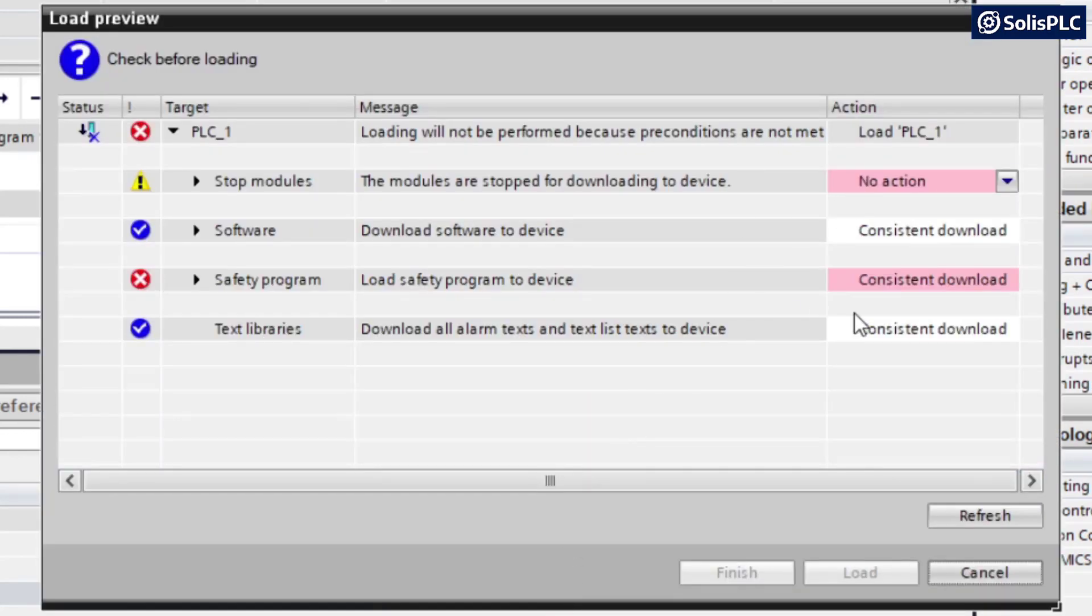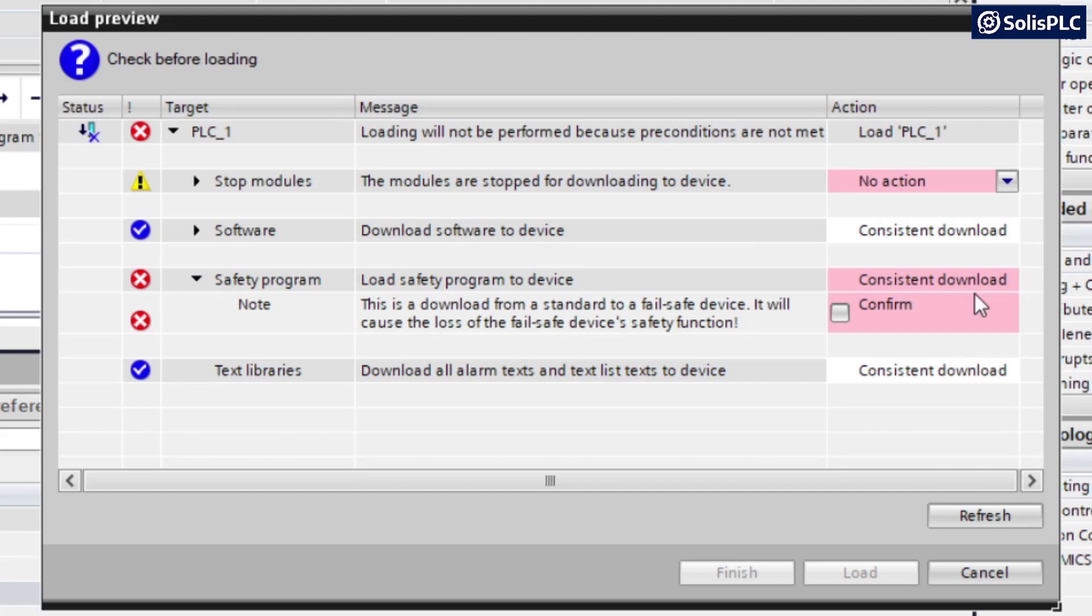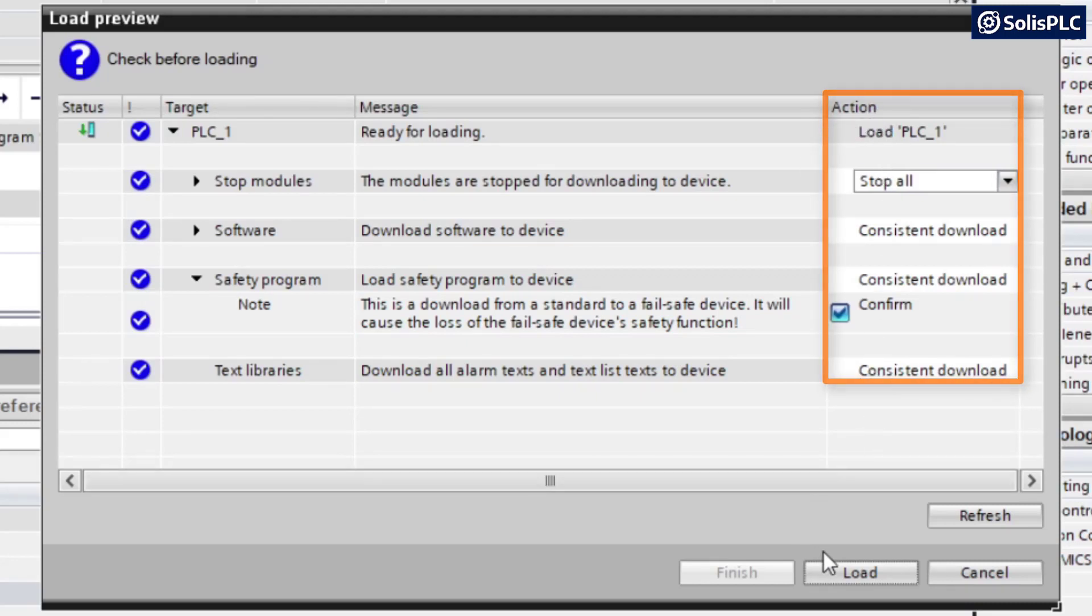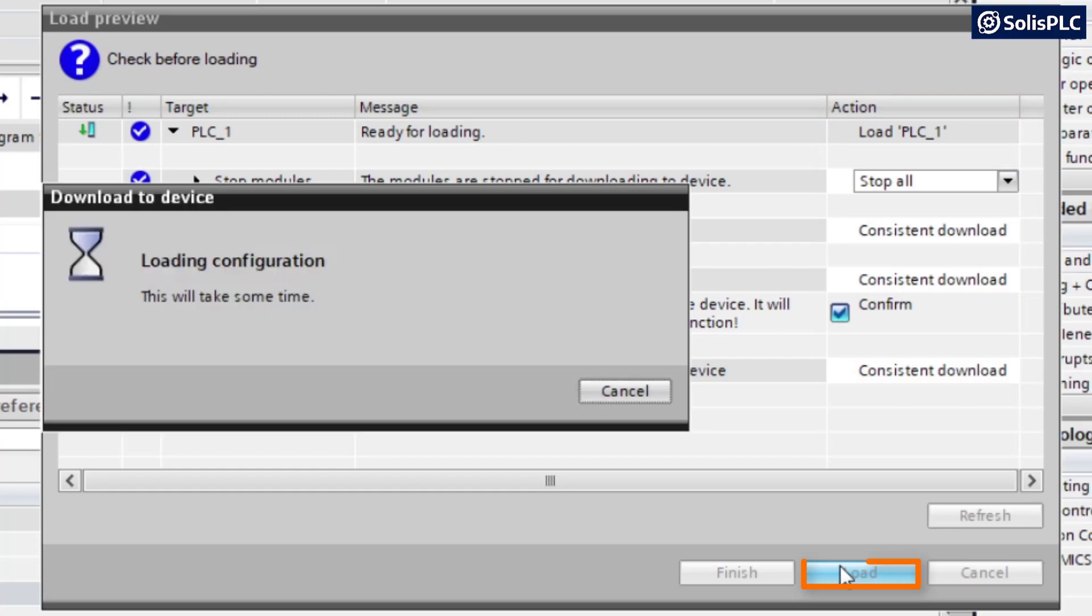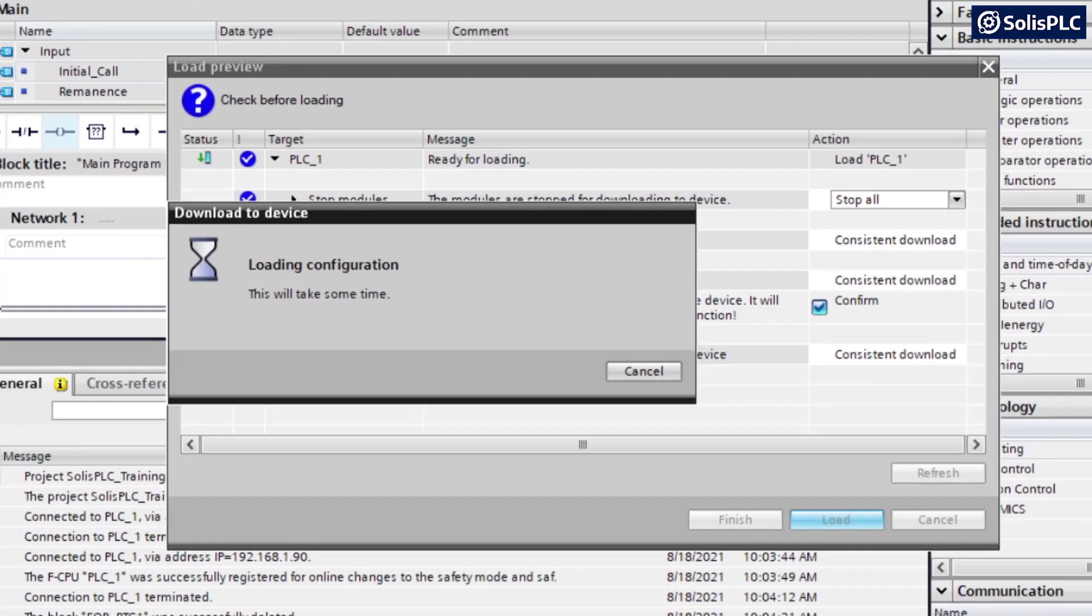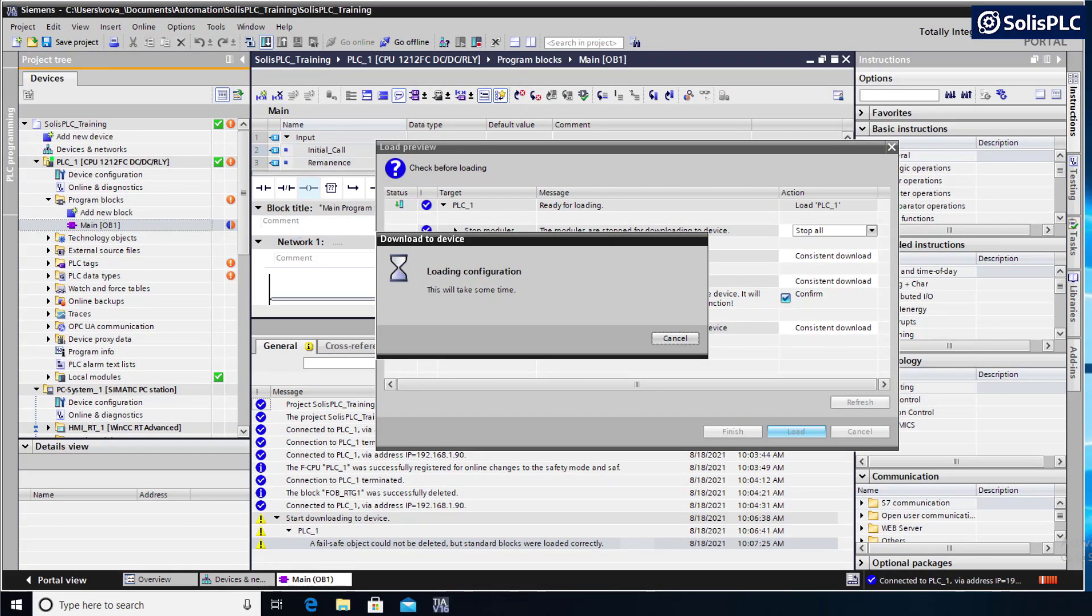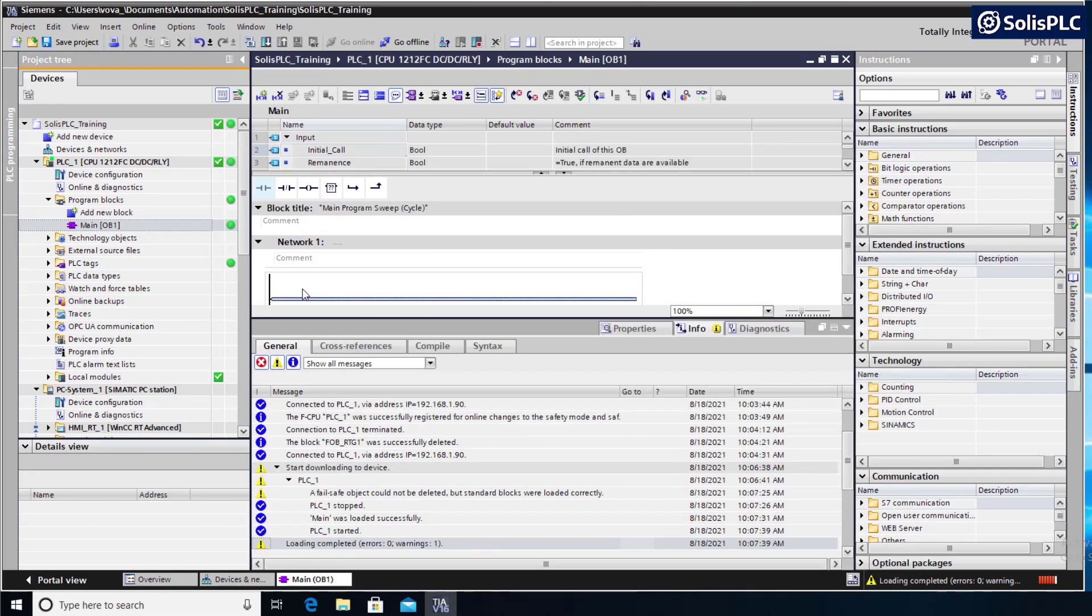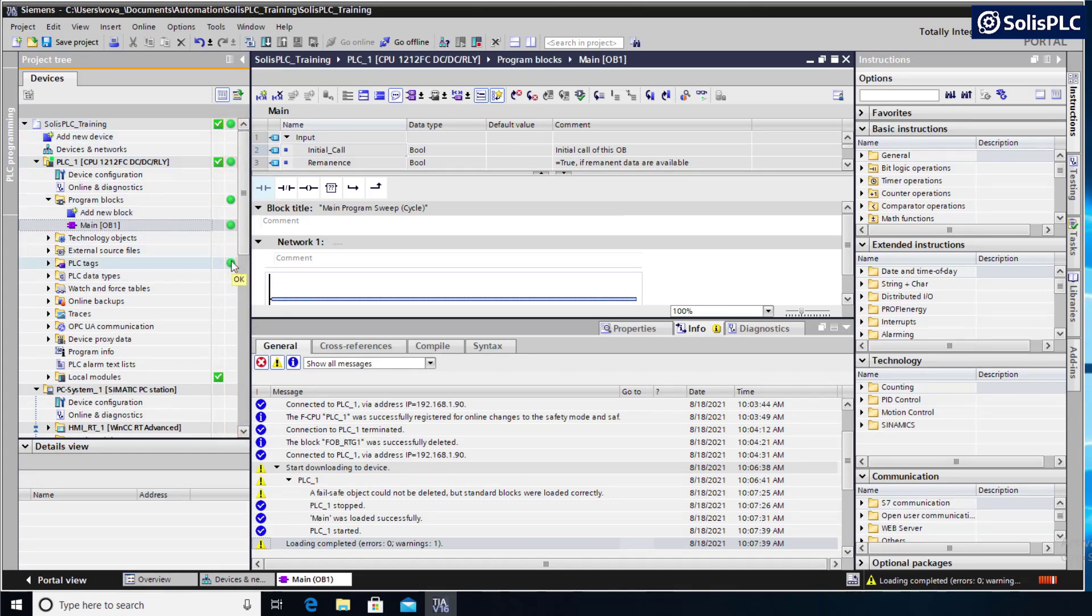You'll notice it's going to give us a couple of warnings. Number one, the safety program. Since I have a safety PLC, I will have to confirm the download. Here are the Stop Modules. We can stop all of them, and then we can load. You may encounter different errors, but you should be very easily able to resolve them through the Action tab over here. Last but not least, we're going to press on Load and we should be able to configure the PLC and match what we have in our project. Once the download is complete, you'll notice that we are now getting all green checkboxes that say OK when you mouse over them. That's exactly what you want to see when you're going online and downloading to your processor for the first time.